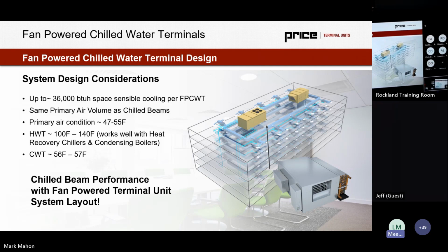Now, when we look at this type of product, really my high-level elevator pitch for anybody, and we just talked a lot about chilled beams, it's chilled beam performance with a fan-powered terminal unit layout. So we're still seeing the same primary air volume as chilled beams, the same primary air conditions as chilled beams.